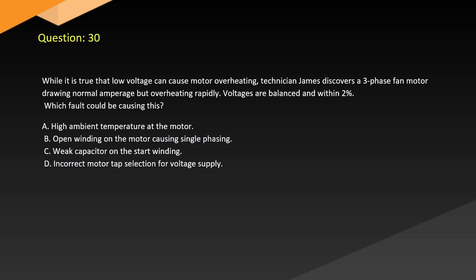Question 30. While it is true that low voltage can cause motor overheating, technician James discovers a three-phase fan motor drawing normal amperage but overheating rapidly. Voltages are balanced and within 2%. Which fault could be causing this? A. High ambient temperature at the motor. B. Open winding on the motor causing single phasing. C. Weak capacitor on the start winding. D. Incorrect motor tap selection for voltage supply.